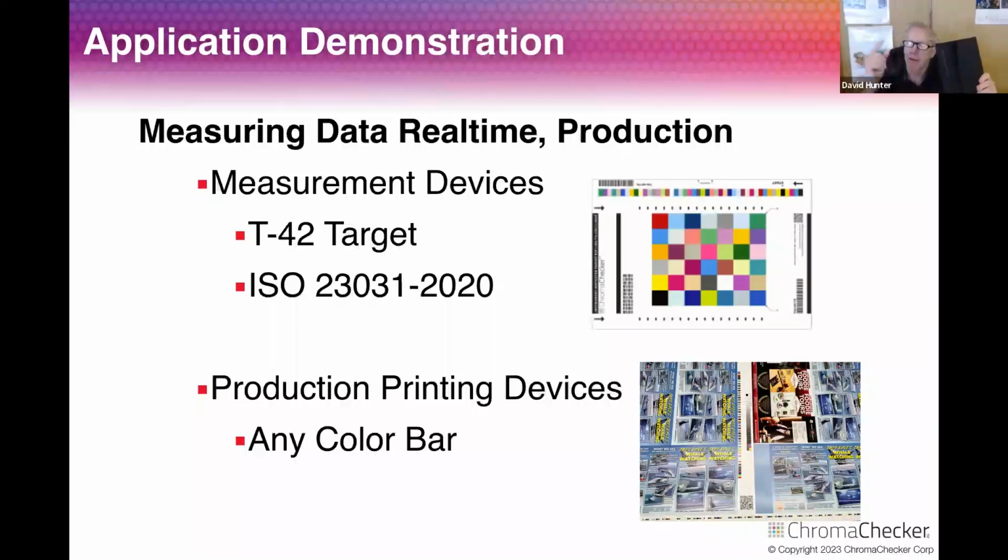And then the ChromaChecker software builds a baseline of how this instrument measures color. And then over time, you can set a reminder to remind me every month or every week, if you want, to remeasure this target. So you remeasure this target with your instruments, let's say every month, and it checks back to the baseline to tell you what the accuracy is of how well this instrument is performing over time.